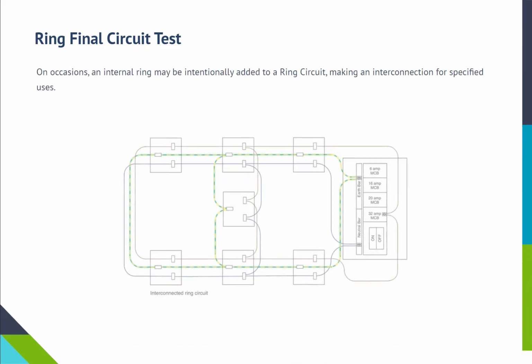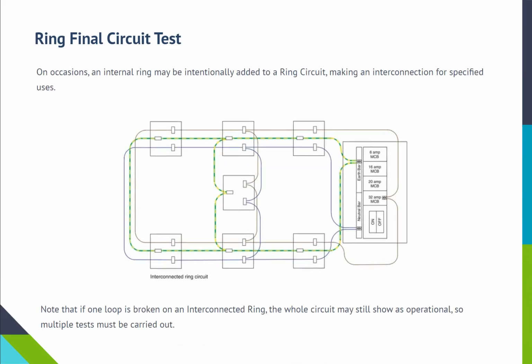On occasions, an internal ring may be intentionally added to a ring circuit, making an interconnection for specified uses. Note that if one loop is broken on an interconnected ring, the whole circuit may still show as operational, so multiple tests must be carried out.